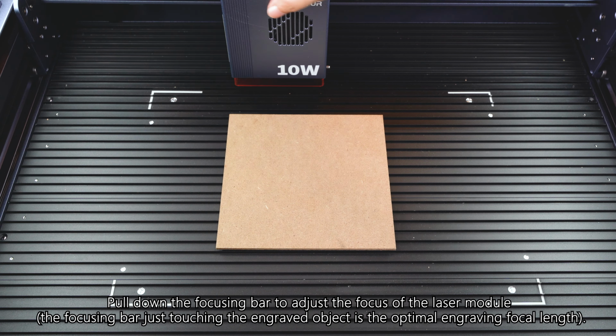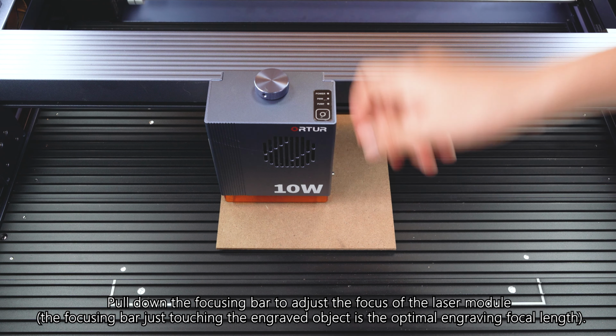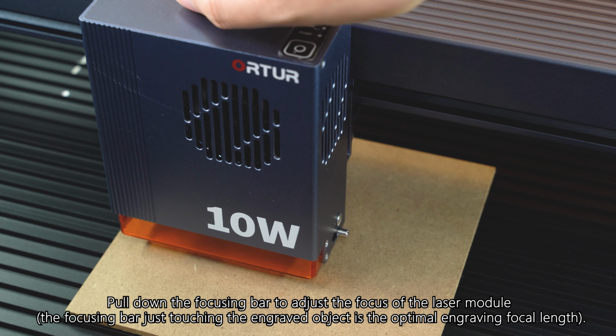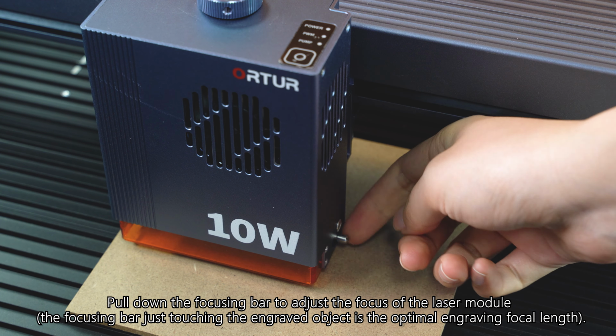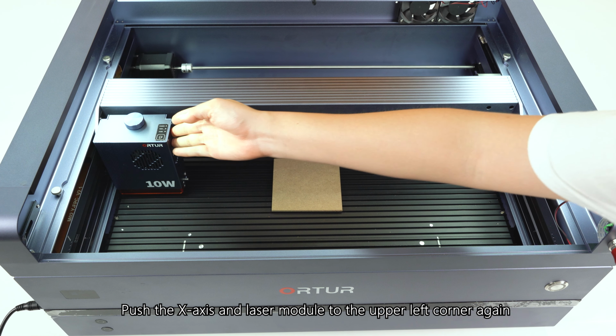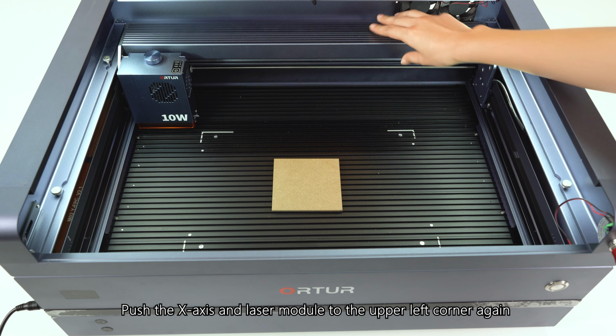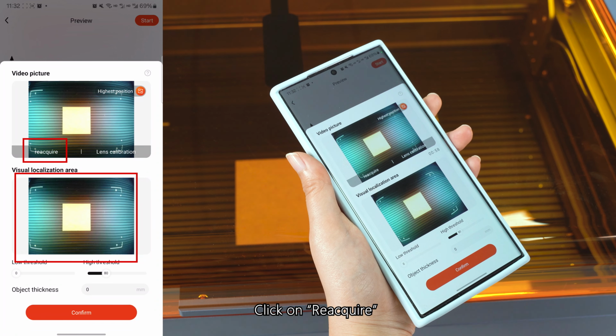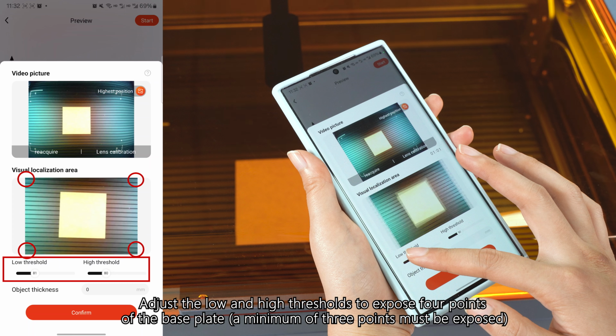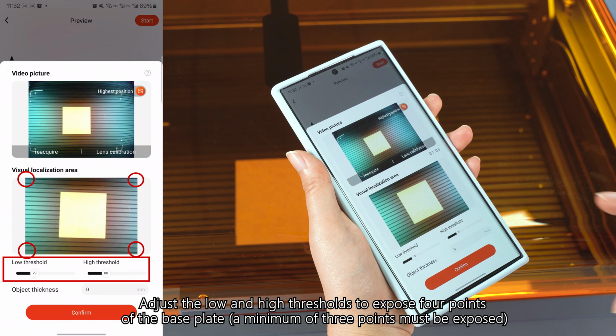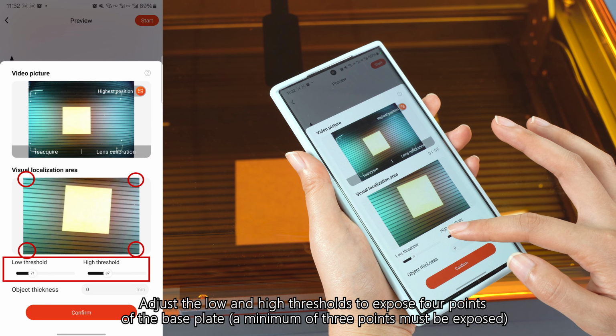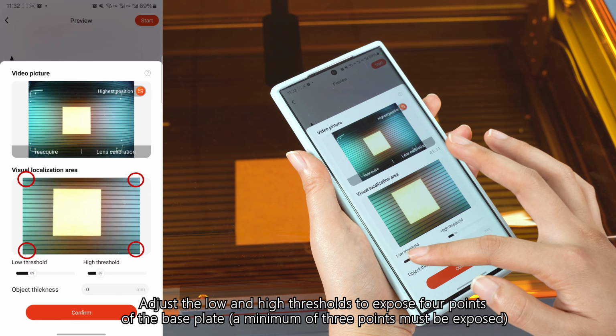Pull down the focusing bar to adjust the focus of the laser module. The focusing bar just touching the engraved object is the optimal engraving focal length. Push the X-axis and laser module to the upper left corner again. Click on Reacquire. Adjust the low and high thresholds to expose 4 points of the base plate. A minimum of 3 points must be exposed.